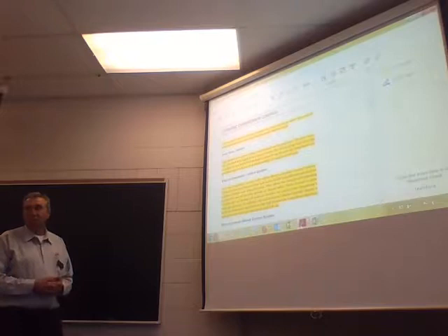Dynamic compressor controls. We've talked about a dynamic compressor. The method is inlet vane control. This method uses a smaller size dynamic air compressor. The inlet vanes are controlled by a signal from the air receiver. The disadvantage with this type of control is that if the load demand is reduced significantly, the compressor can go into surge.